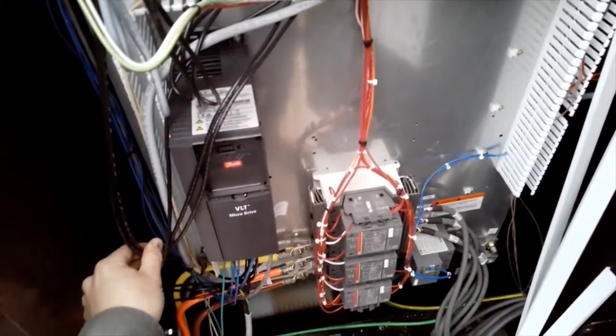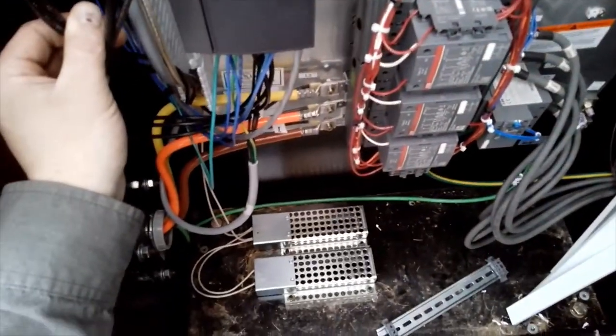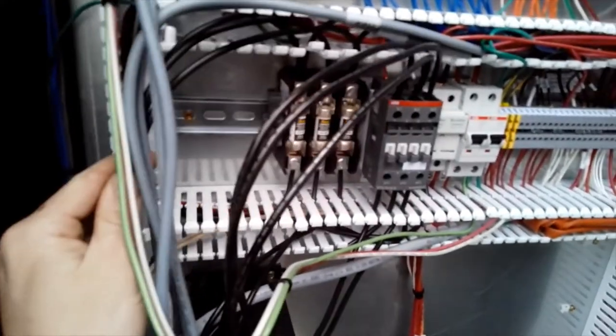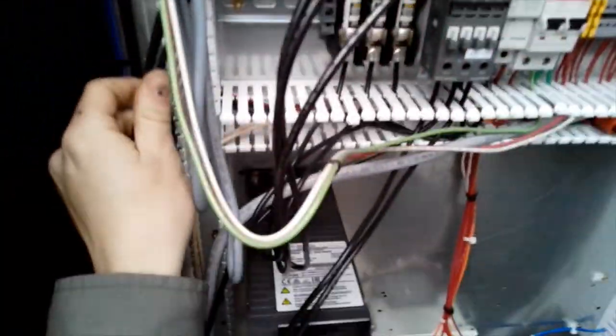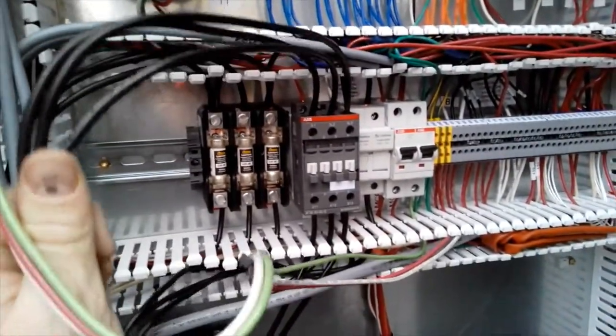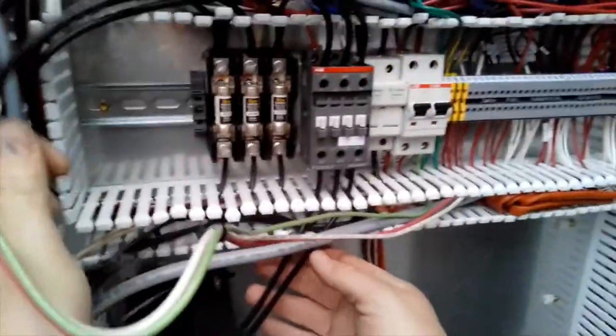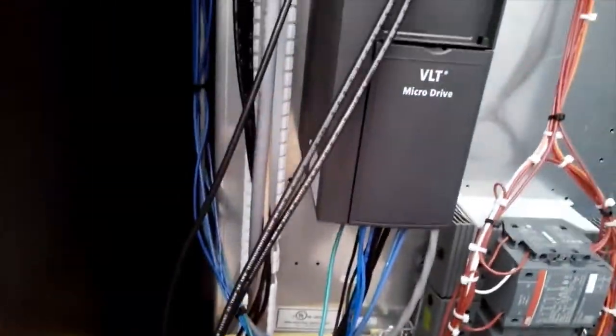All right, so the first thing we need to do is trace down this wiring. It looks like it goes from the incoming power, grab these wires, up to the top of those fuses. From the bottom of those fuses, it goes to the top of this contactor, and from that contactor, it goes to the input of the drive.